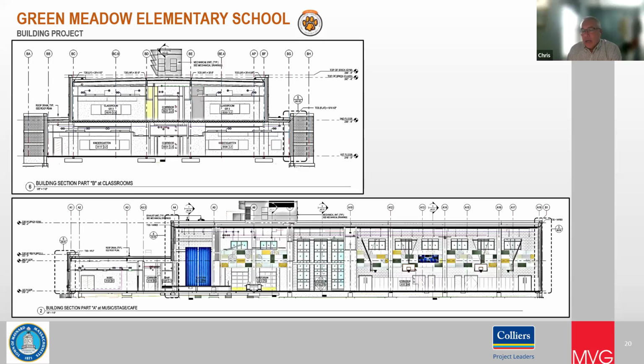Once the school is operational, facilities will be able to go in, because there's commissioning taking place, trending, and the commissioning agent will come in 10 months afterwards and talk with the staff about how the system is running. They'll have access to everything, talk with facilities, and if set points need to be adjusted, those things can take place, because you might find the building is so efficient that you don't need as much heat.